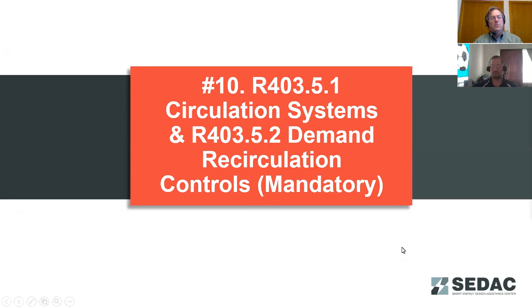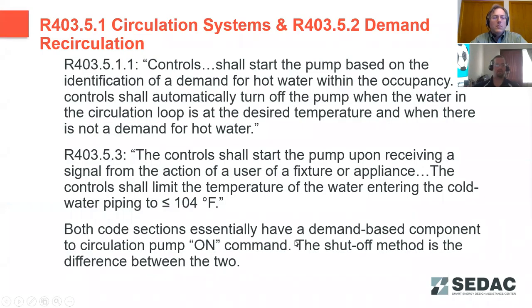Moving on, looking at domestic water circulation and demand recirculation controls. We want to note here specifically for both these systems, there is a demand component. R403.5.1 and R403.5.2, primary being for circulation systems, the second being for demand recirculation systems. Both of these include the requirement that before that circulating pump kicks on, there needs to be an identified demand for hot water flow.